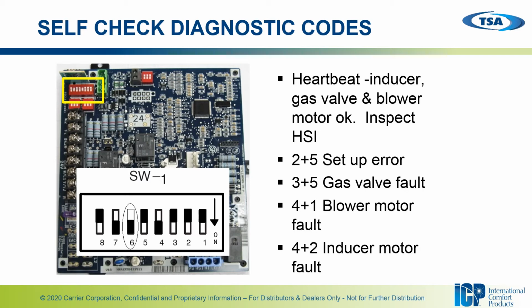If there was an issue at the end of the self-check cycle, you will get a fault code as follows. A 2+5 will indicate some sort of setup error, which typically means a dip switch or something like that is set improperly on the control board. A 3+5 is going to give you a gas valve fault, which could be a faulty gas valve or some sort of faulty wiring or connection between the control board and the gas valve. 4+1 is going to be a blower motor fault. Again, it could be an issue with the blower motor itself or just a connection, as there are Molex plug connections between the control board and the blower motor. And a 4+2 is going to be an inducer motor fault. Again, it could be directly related to the inducer motor or a connection between the control board and the inducer motor.